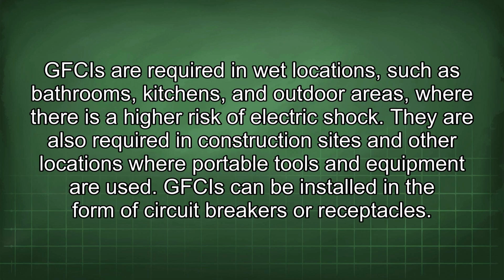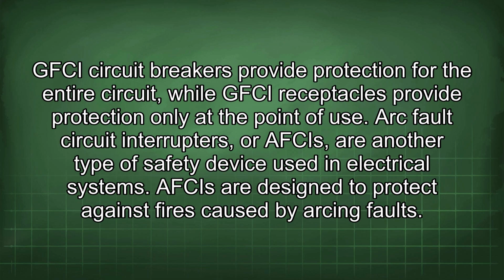GFCIs are required in wet locations such as bathrooms, kitchens, and outdoor areas where there is a higher risk of electric shock. They are also required in construction sites and other locations where portable tools and equipment are used. GFCIs can be installed in the form of circuit breakers or receptacles. GFCI circuit breakers provide protection for the entire circuit, while GFCI receptacles provide protection only at the point of use.